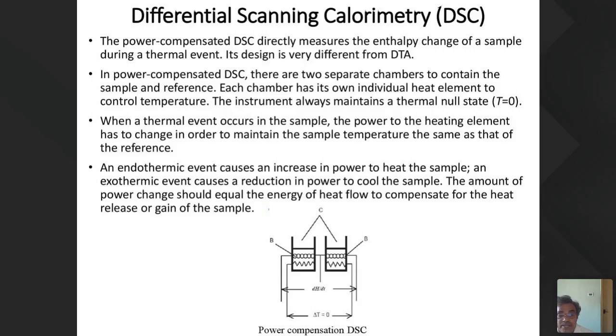This event is correlated. An endothermic event causes an increase in power to heat the sample. An exothermic event causes a reduction in power to heat. The amount of power change should be equal to the energy of heat flow to compensate for the heat release or gain of the sample. That means, depending upon the change in temperature, the event will change. By taking the temperature difference, you can study the event.